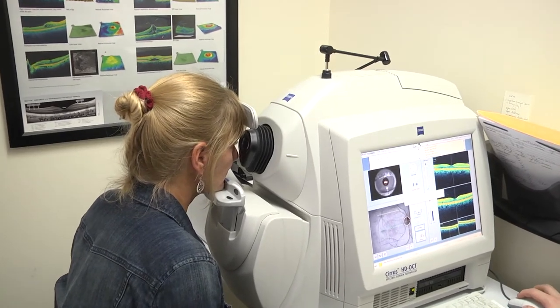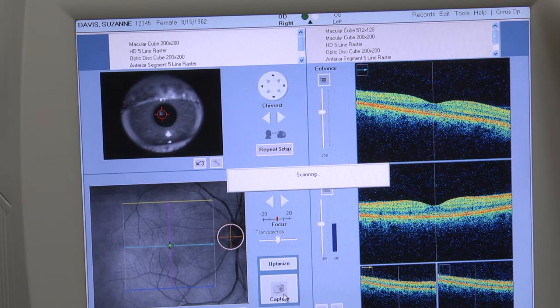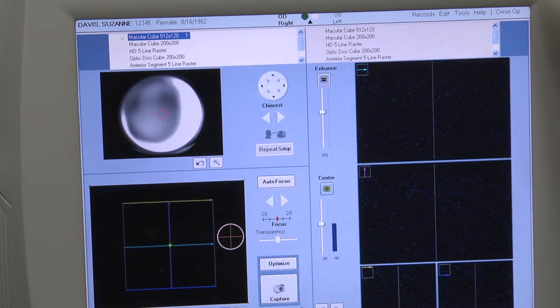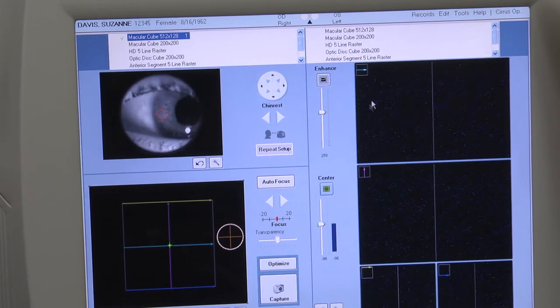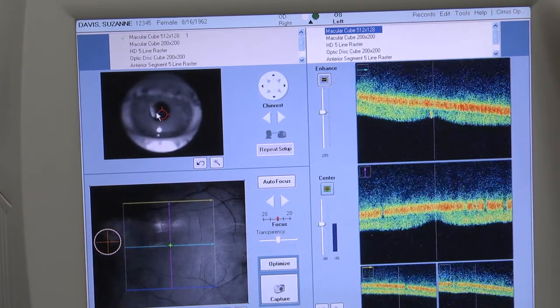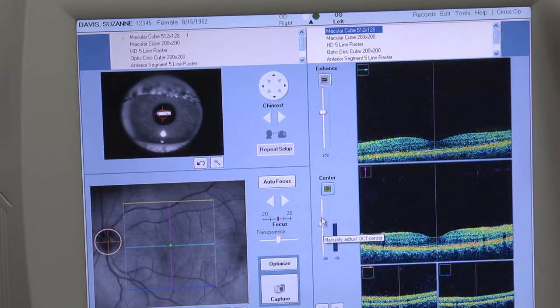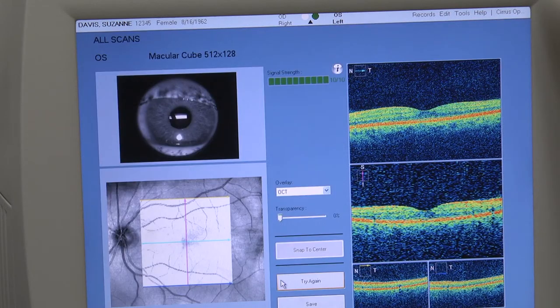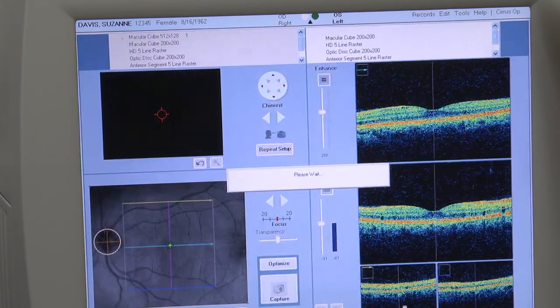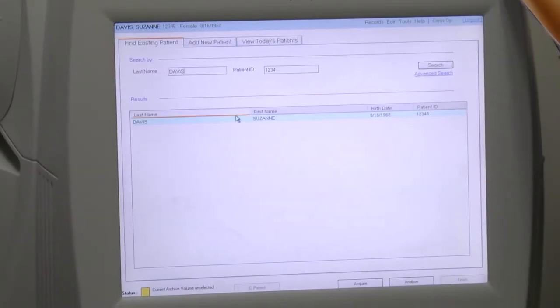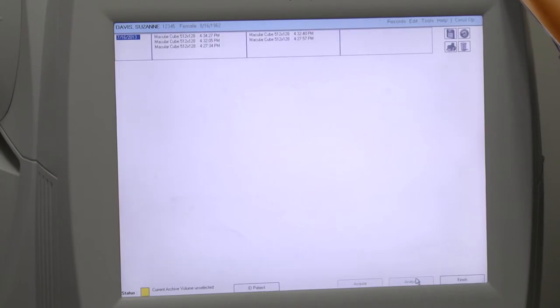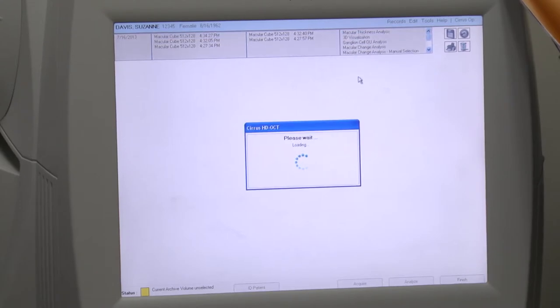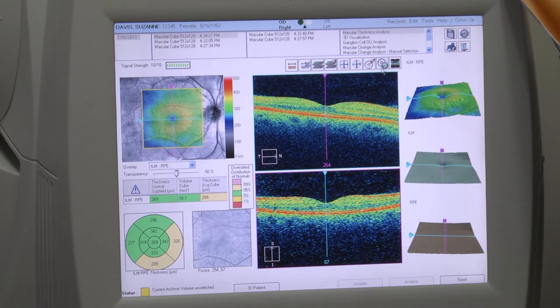Ask them to hold it, do not blink, don't move. Once it's done, you'll review the picture. If you're happy with it, hit Save. Once you hit Save, it will automatically have you switch to the other eye — proceed with the same steps as the first eye. Once you're happy with that, hit Save, then hit Finish. It will have the patient's name highlighted, and you'll want to click Analyze. Once you hit Analyze, it will take you to the Review screen. Select your test from the top of the screen for the eye that you did, then hit Print, and repeat that for the second eye. Once done, take your printouts and place them in the chart behind the appropriate tab. Now you can take your patient back to the exam room to have the doctor review the test with them.